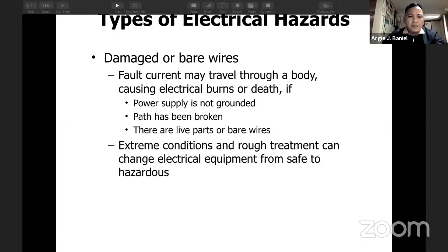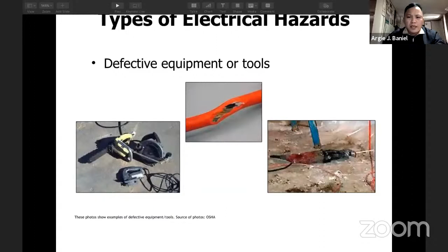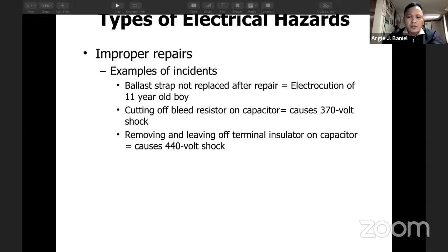So type of electrical hazards, we have the damage or bare wires. Fault current may travel through a body which cause electrical burns or death if power supply is not grounded. Extreme conditions and rough treatment can change electrical equipment from safe to hazardous. Yan yung mga defective equipment or tools. So napakadelikado niyan, especially to construction site. Improper repairs, examples of incidents. Halimbawa, ballast strap not replaced after repair, electrocution of 11 years old boy, cutting of bleed resistor and capacitor which causes a 370 volt shock, removing and leaving of terminal insulator on capacitor which causes a 440 volt shock.